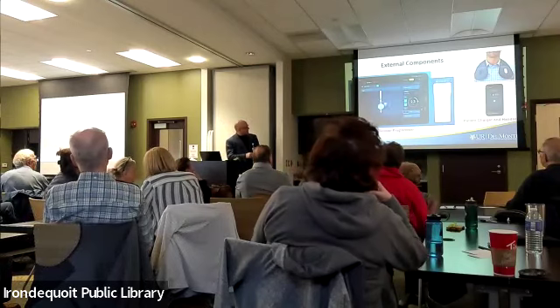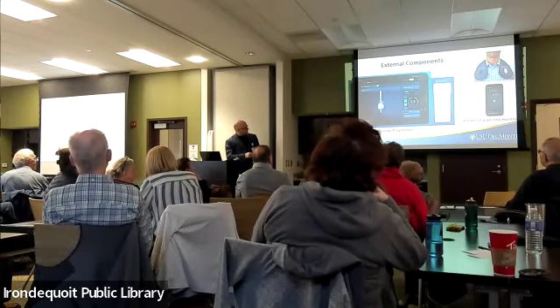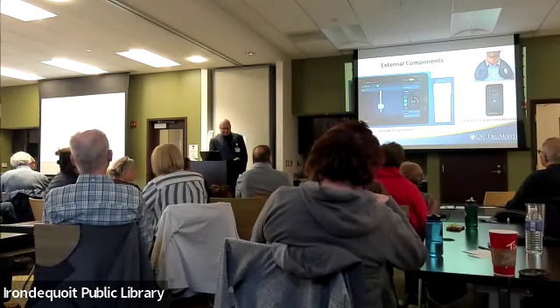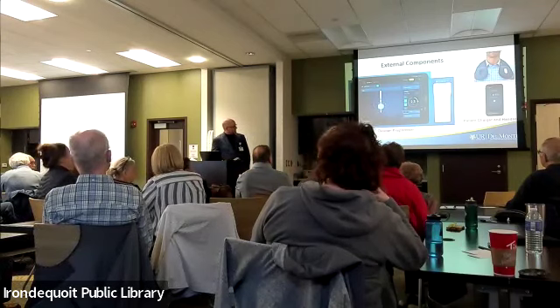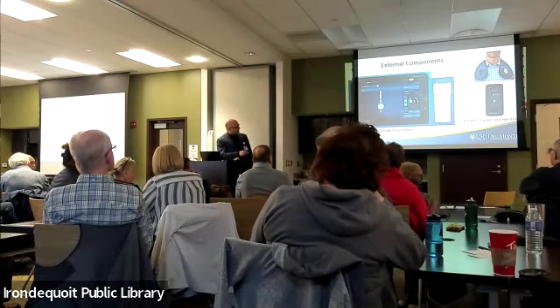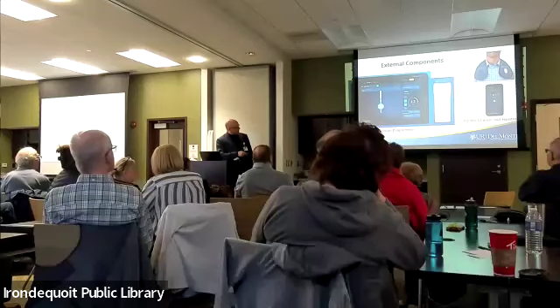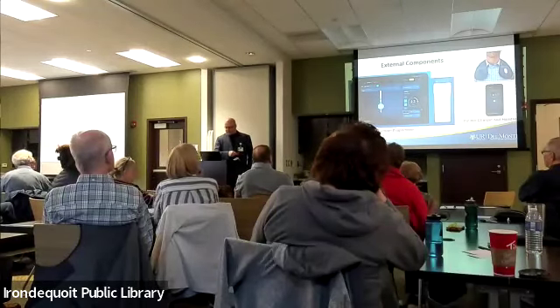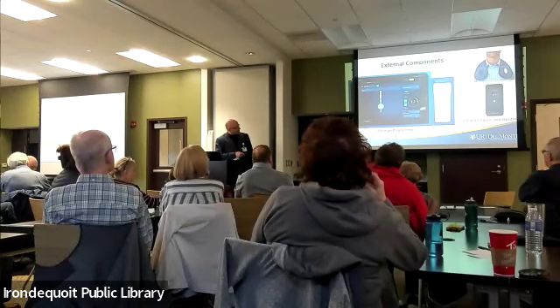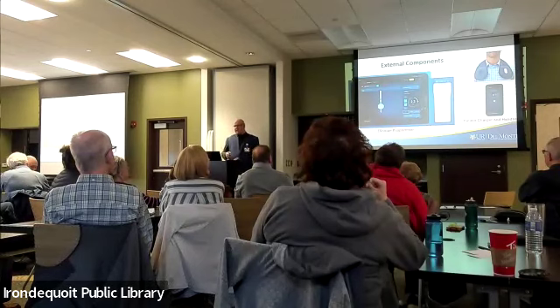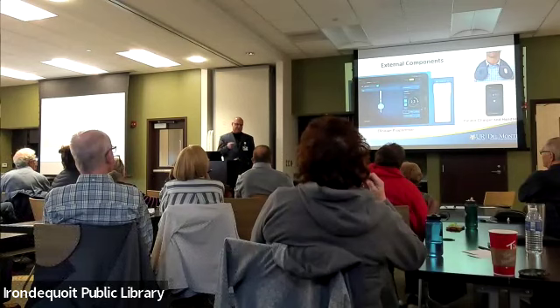and this is the first time that it shows how each individual contact can form this field. It's like a circular or spherical field of electrical stimulation, and we can adjust it. We can adjust different factors of that stimulation field, the actual current. We can adjust how long that current is on for in microseconds, and we can adjust how many times per second those pulses are provided. So 90 times per second, 200 times per second, we can make those adjustments.